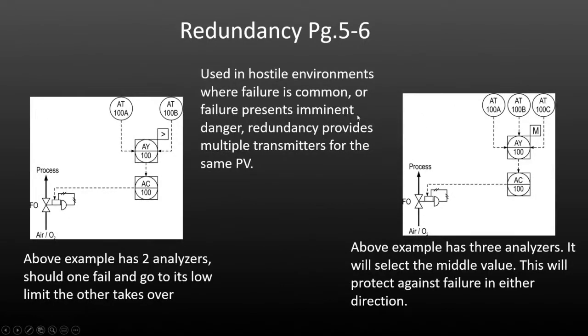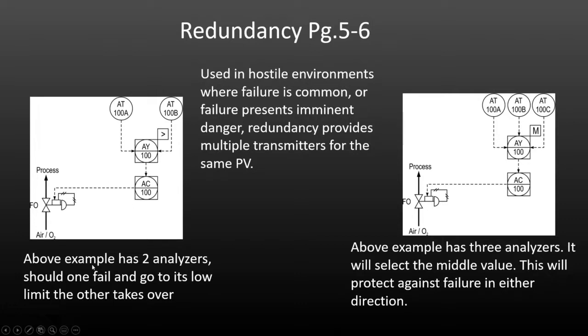Redundancy is one of the more common applications for selective control. In hostile environments where failure is common or could pose imminent danger, redundancy provides multiple transmitters for the same process variable, and one can take over should the other fail. There's an example where we have two analyzers — should one fail and go low, you can select the failure action to drive high or drive low depending on your process. In this case, should the analyzer fail, it's going to drive low and create a low signal.